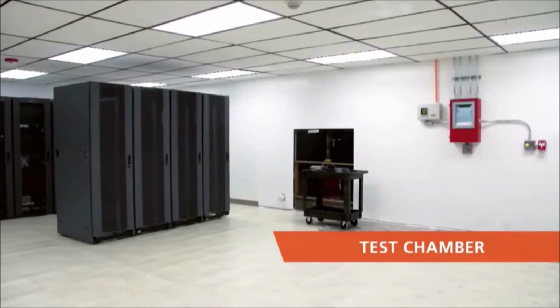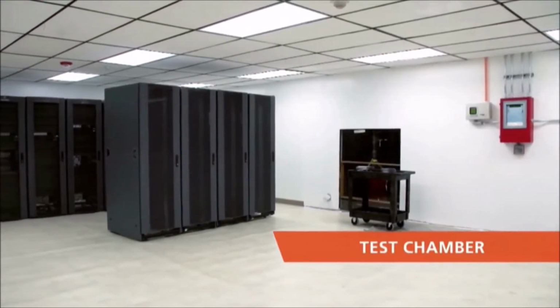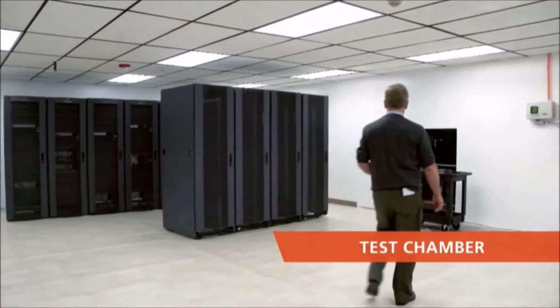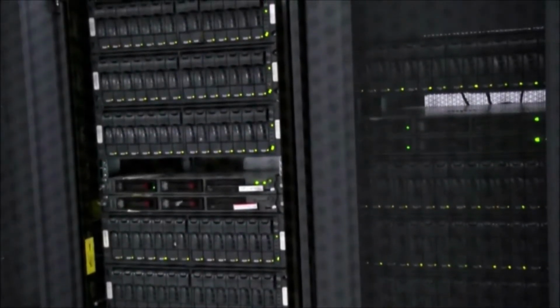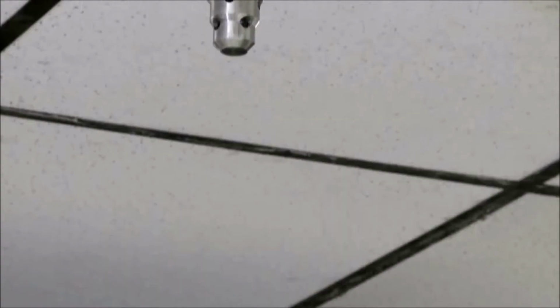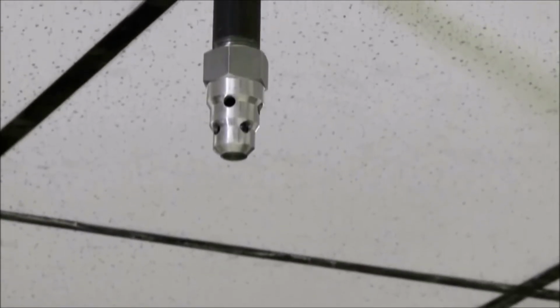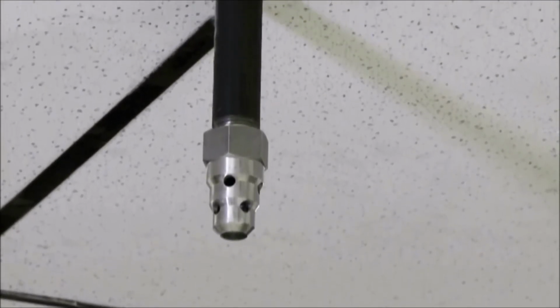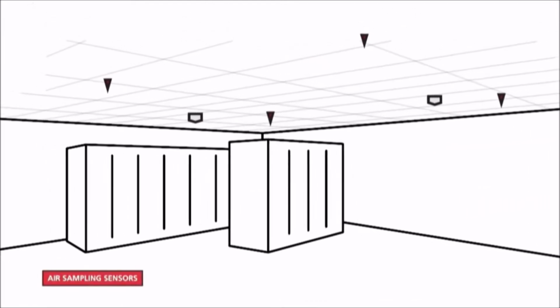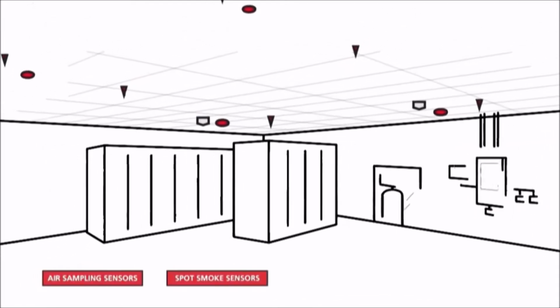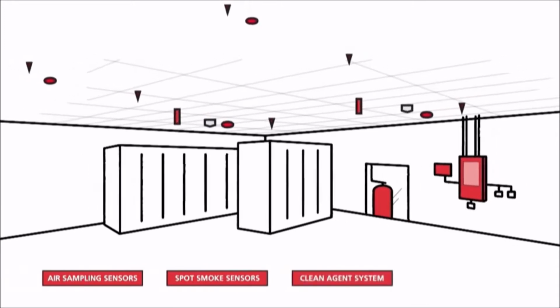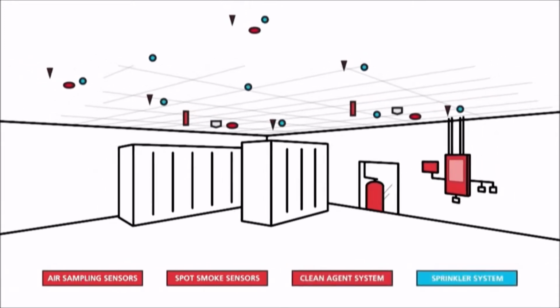To demonstrate the difference, we've replicated a data center in this fire testing facility. Typically, a data center fire would start inside one of these server cabinets. This type of enclosed fire is tough to extinguish using sprinklers alone, but it's an ideal situation for clean agent fire suppression systems. The room is equipped with Kidde air sampling and spot smoke sensors, plus the clean agent fire suppression system and 9 water sprinklers.